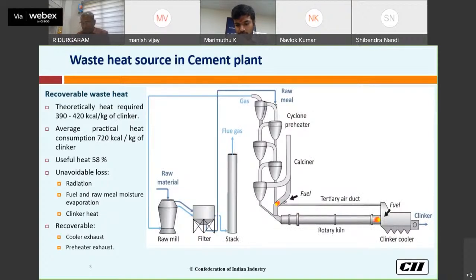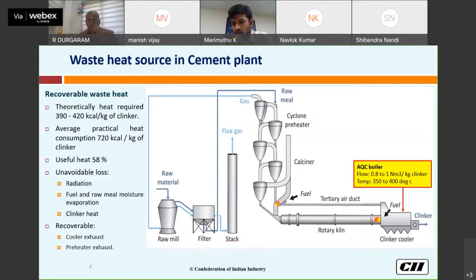So this is the simple process diagram from the clinker cooler and preheater stages. In this, on the right side, you can see the AQC boiler is normally designed for a flow of 0.8 to 1 Nm³ per kg clinker. There we will have heat at a temperature of around 350 to 400 degrees centigrade. And in the case of the PH boiler, we have a flow of 1.4 to 1.6 Nm³, and there the temperature is around 280 to 350 degrees. So these systems are already adopted in many of the units.